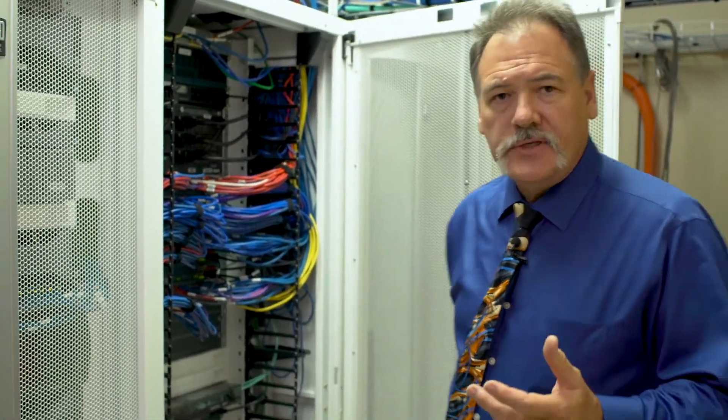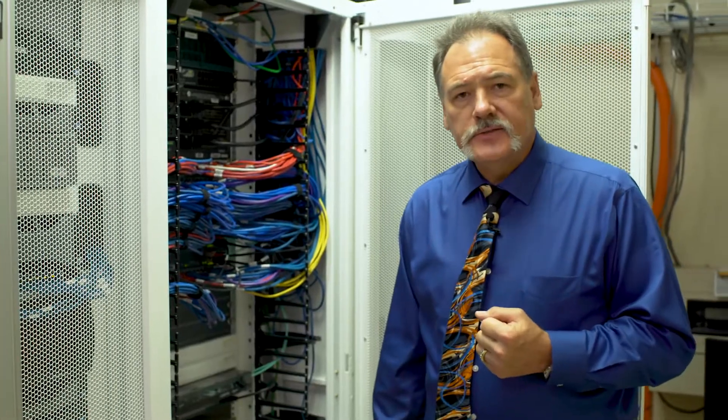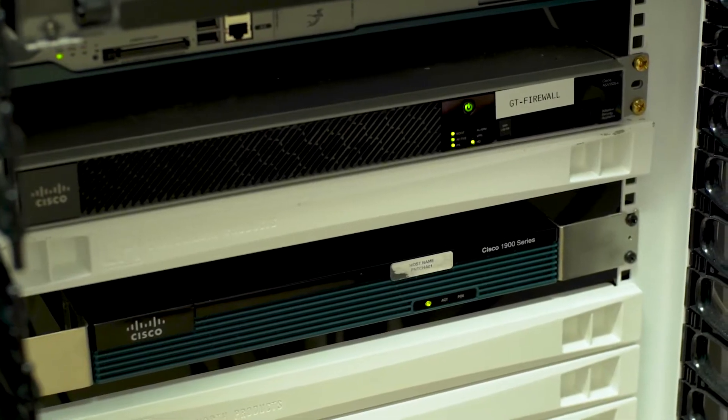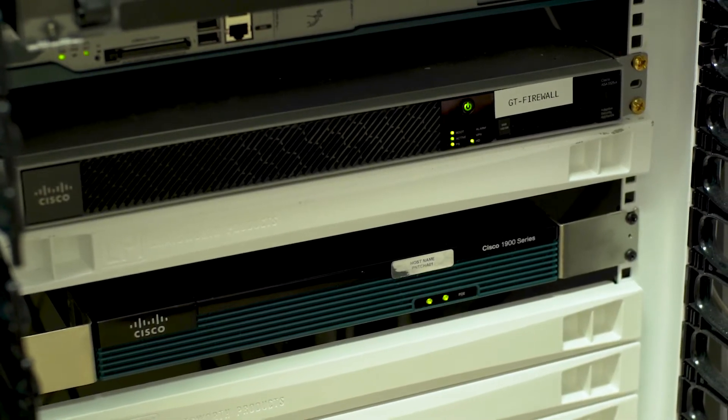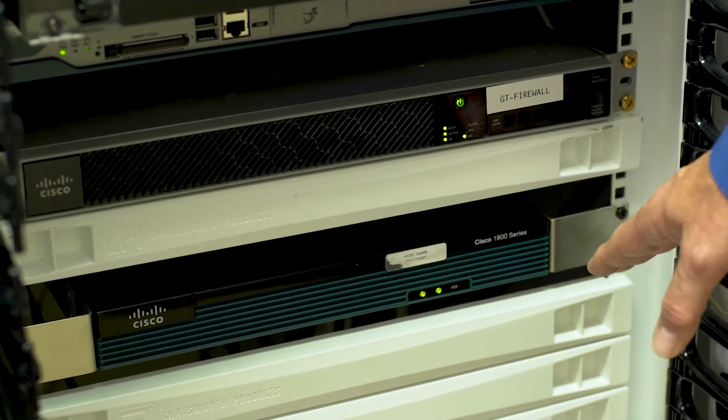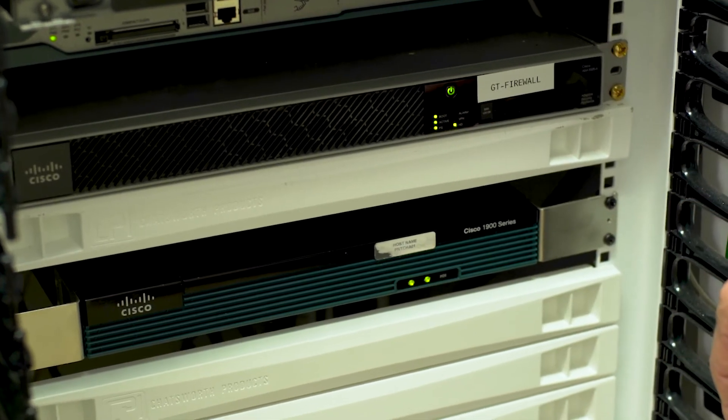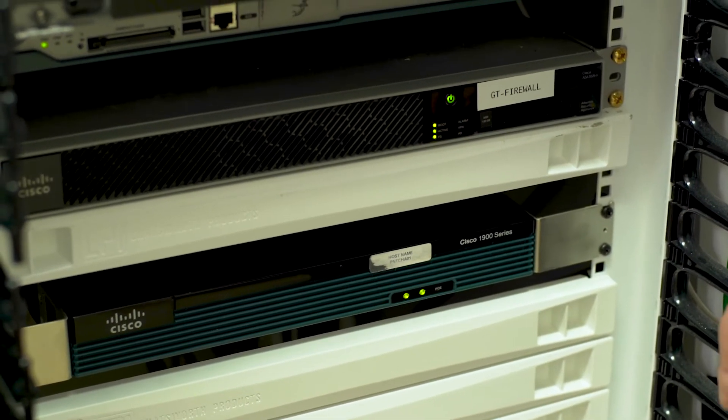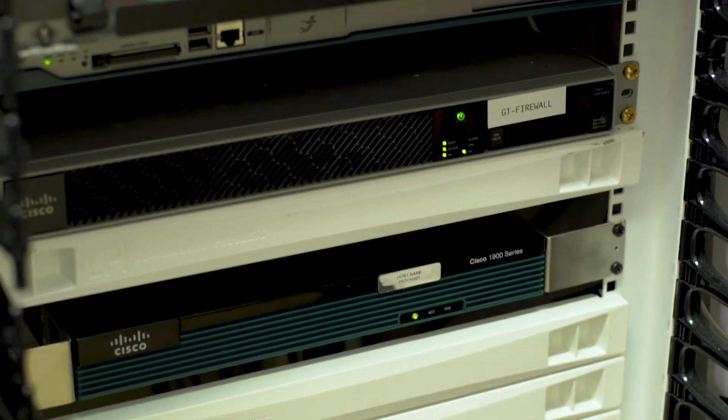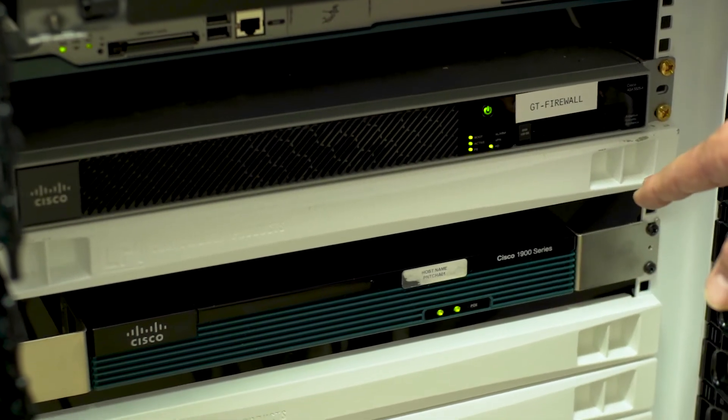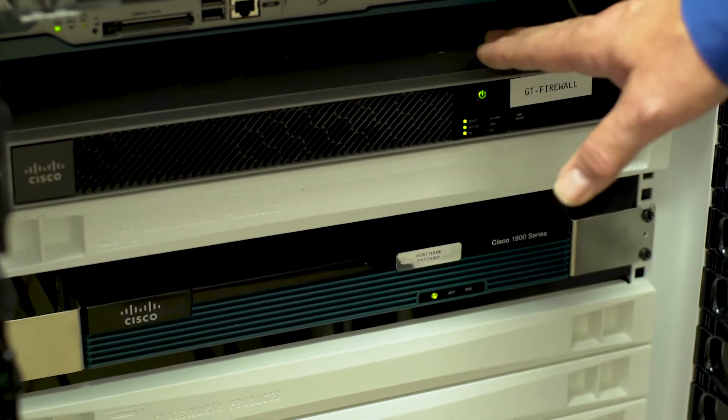One of the key items is how the devices are racked. One of the first challenges that we have is when your folks don't put their devices on the proper U spacing they put it off half of U. That goes through and it makes it where you can't blank around that device such as what we have here.